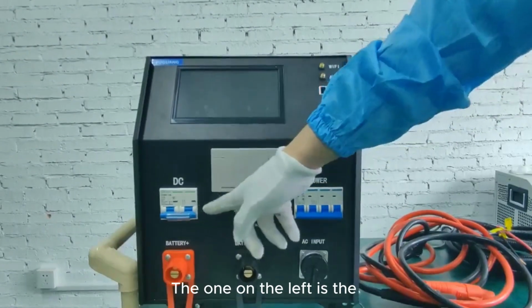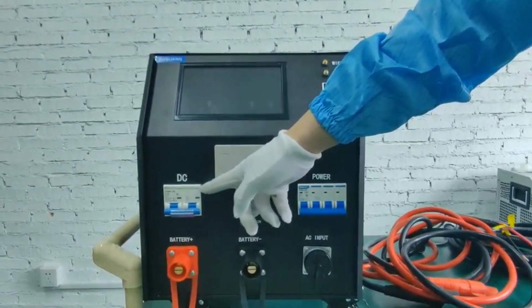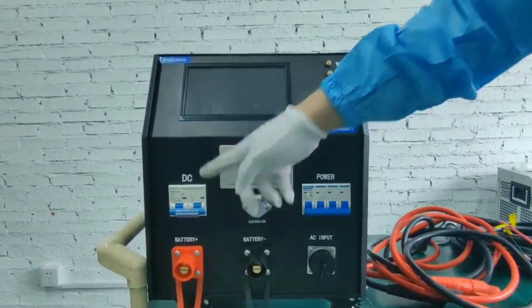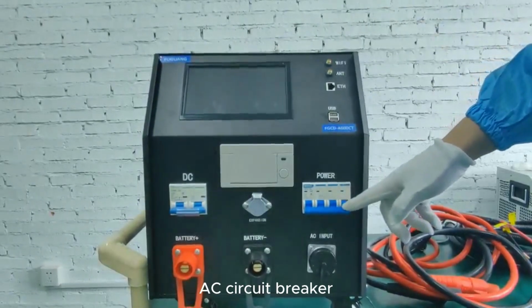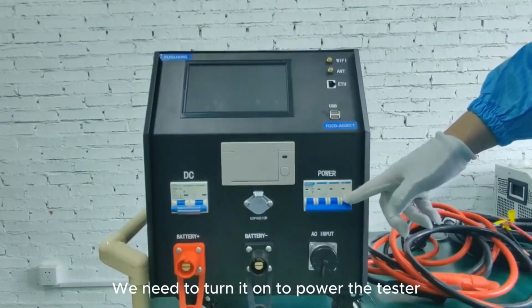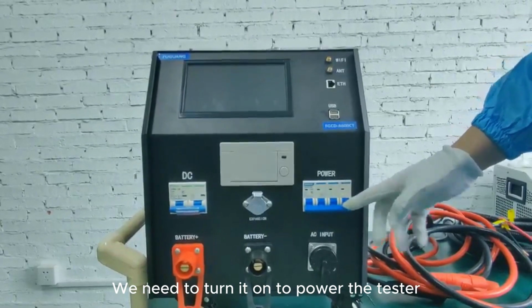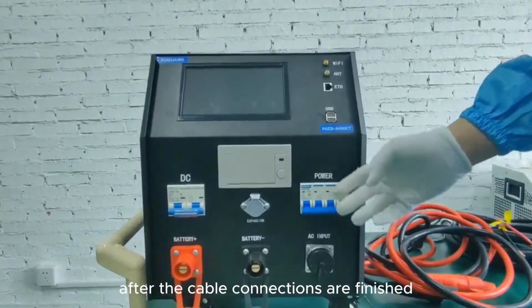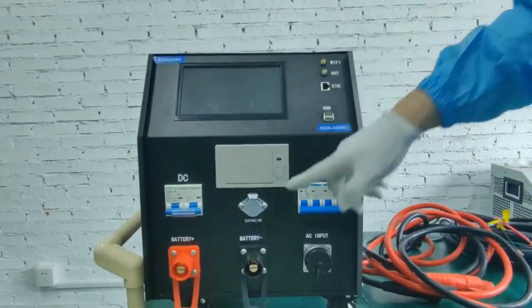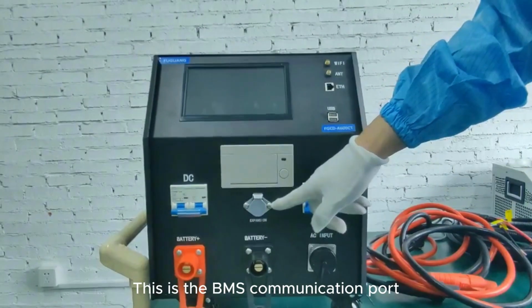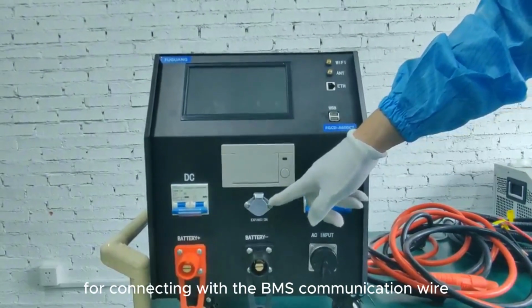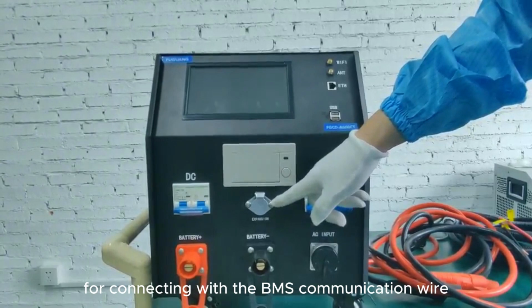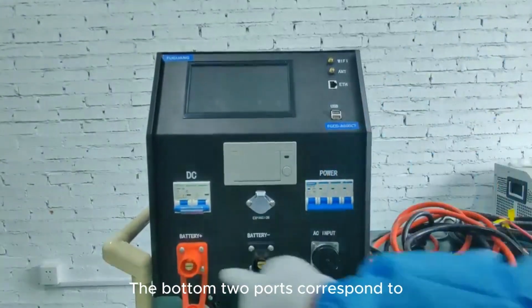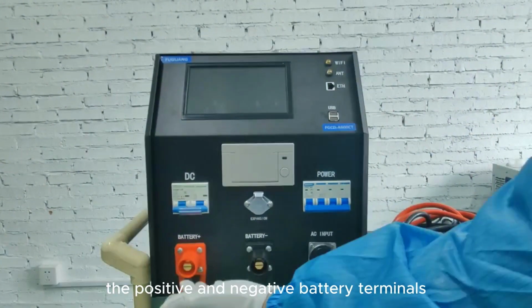The one on the left is the DC circuit breaker. The one on the right is AC circuit breaker. We need to turn it on to power the tester after the cable connections are finished. This is the BMS communication port for connecting with the BMS communication wire. The bottom 2 ports correspond to the positive and negative battery terminals.